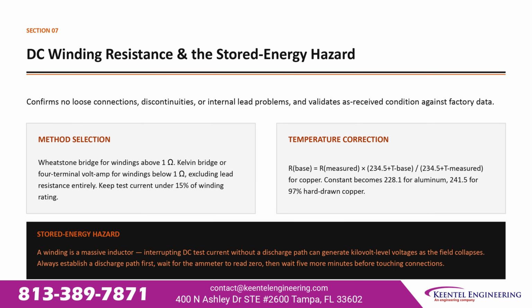Winding resistance testing confirms there are no loose connections, discontinuities, or internal lead problems, and validates as-received condition against factory data. For method selection, use a Wheatstone bridge for windings above 1 ohm and a Kelvin bridge or 4-terminal volt-amp method for windings below 1 ohm, which excludes lead resistance entirely. Keep test current under 15% of winding rating.